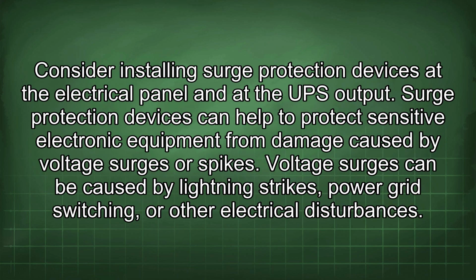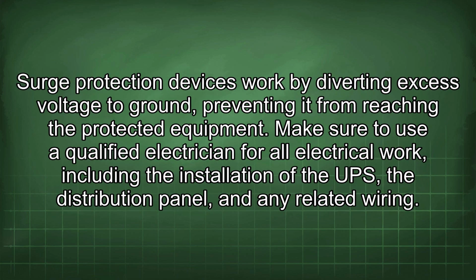Consider installing surge protection devices at the electrical panel and at the UPS output. Surge protection devices can help to protect sensitive electronic equipment from damage caused by voltage surges or spikes. Voltage surges can be caused by lightning strikes, power grid switching, or other electrical disturbances. Surge protection devices work by diverting excess voltage to ground, preventing it from reaching the protected equipment.